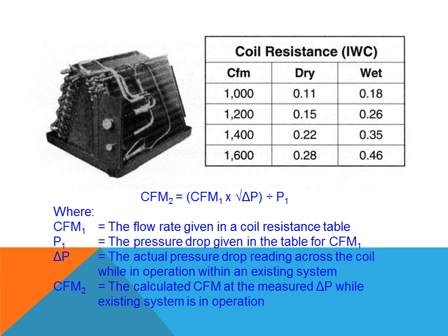Now going to the air conditioning equipment, we're sizing it up. And as we size up the components, we need to look at first how much CFM is going to be needed to go through the house. As a rule of thumb, well, it's not really a rule of thumb, for every ton of cooling, every ton of refrigeration, which is 12,000 BTUs, it is required to have 400 CFM for every ton.